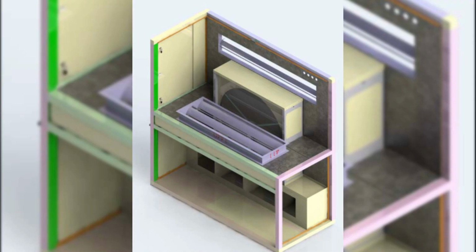2. Variable volume requirement. Variable volume units are required if the mechanical DX cooling capacity exceeds 65,000 BTU per hour or the fan horsepower of dual-temperature air handling units is over 1/4 of a horsepower, per ASHRAE standards. 3. Exceptions. Constant volume units may be used for historic buildings or for repairs where extensive revisions or insufficient space exists. However, more efficient systems are preferred if technically feasible to meet New York City's energy-saving mandates. 4. Preference. Heat pump units are preferred over dual-temperature air handling units.